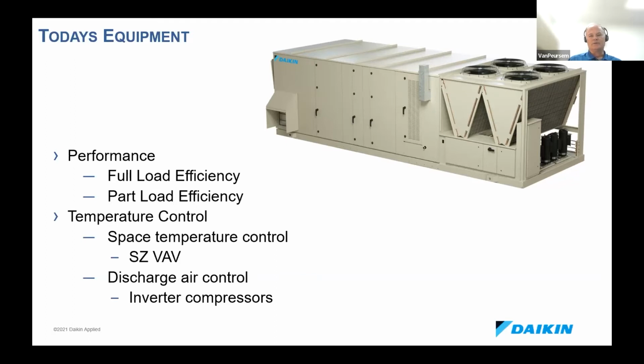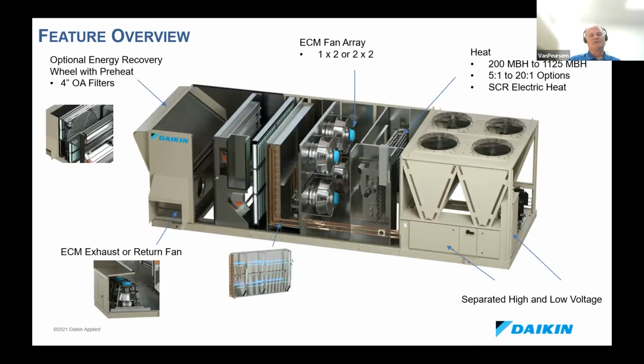More and more people are doing tighter discharge air control with equipment, adding items such as inverter compressors. In the last 10 years, the inverter compressor has become the mainstay, back when we started adding inverter compressors to the equipment in 2010. So taking a look at that technology, what does that do? It adds a lot of different items to further increase the fan efficiencies, such as direct drive ECM plenum fans, 100% modulating, not running at constant volume, but at full proportional control to maintain that airflow through the equipment.